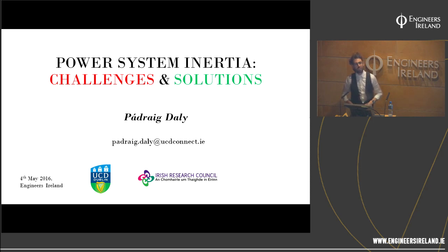So I think we have to look at not just technical solutions that we've seen this evening, but also how we can get the best use out of existing assets, because all you have to do is decouple the turbine. Yeah. And that's straightforward enough. So I think system operators would be more comfortable, shall we say, with machines whose characteristics they're fairly familiar with, than relying on a box of electronics tricks that they're not quite sure will work, because they have a lot of experience with the conventional generators that in fact the frequency response is not what it's supposed to be.